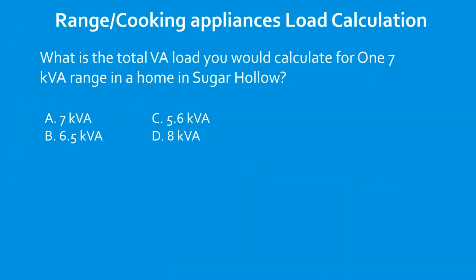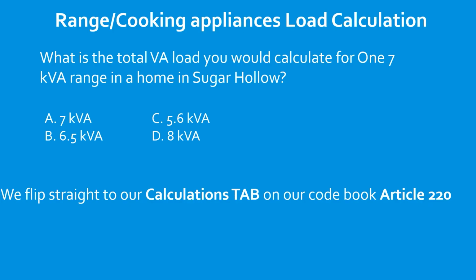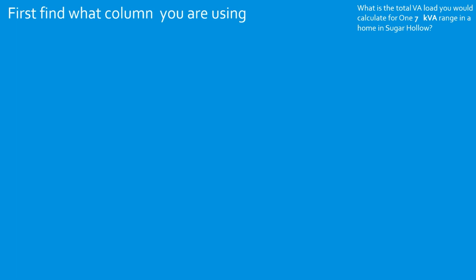What is the total VA load you would calculate for one 7 kVA range in a home in Sugar Hollow? We're going to flip straight to our Calculations tab, Article 220 in our codebook. We're going to head straight to Table 220.55. All right, so the first thing we're going to do is figure out what column we're using. So we reread our question. What's the total VA? One range, 7 kVA. So we look at our table. Where does 7 fall? It falls in column B, doesn't it? So we head to column B.